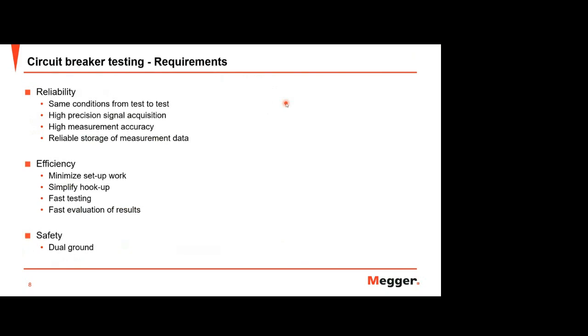And this is the circuit breaker testing requirement. So for testing your circuit breaker, there are many requirements that should be complied with. Whichever form of maintenance approach is selected, the most important goal is to achieve maximum reliability at the lowest possible life cycle cost. This is the goal, as I know from many customers. And since breaker testing is many times based on comparison and trend analysis, it is important to strive to have the same condition from test to test.